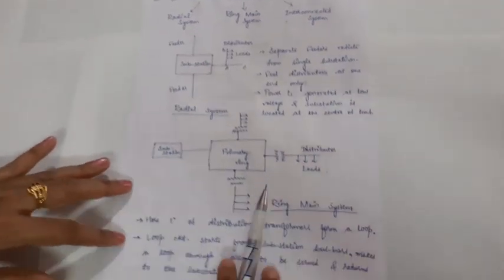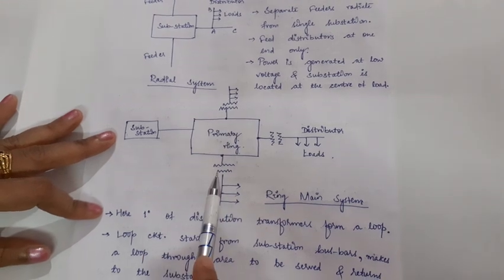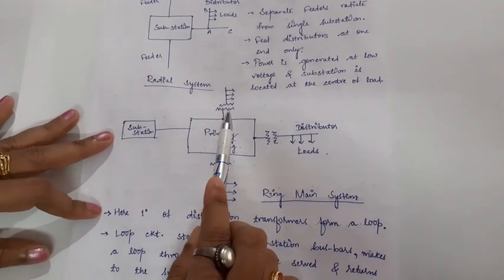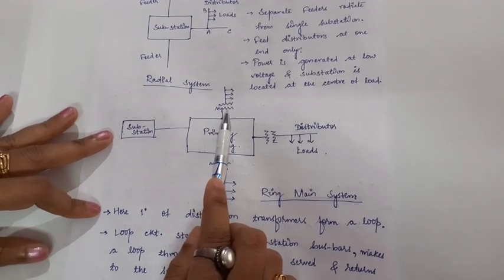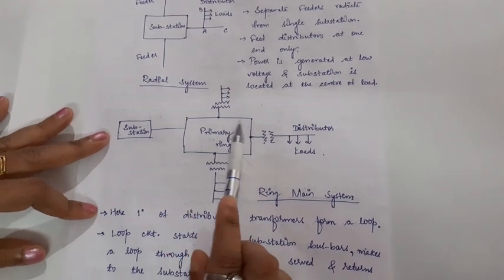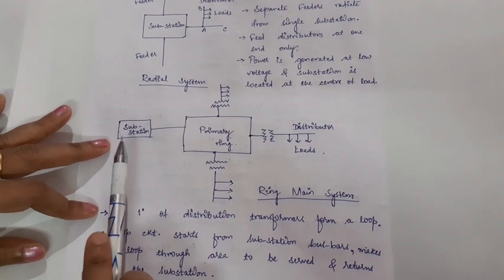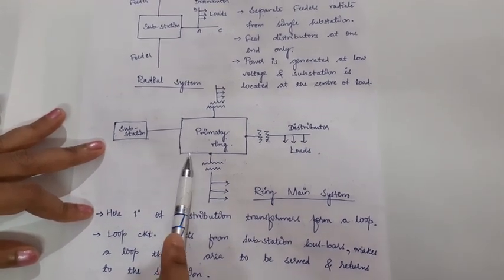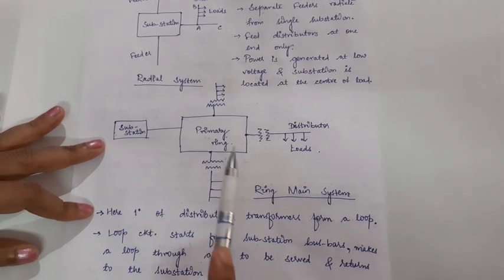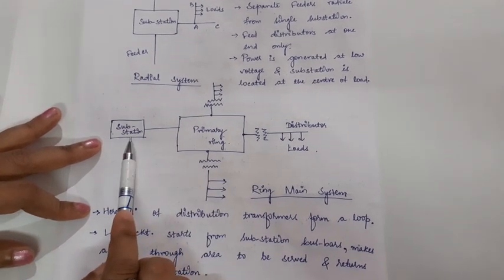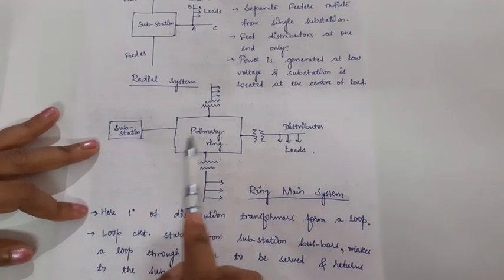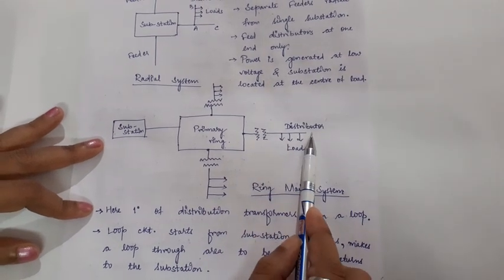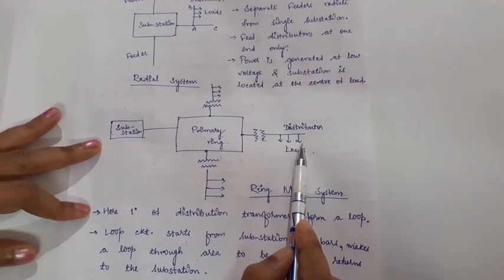In the ring main system, the primary of the distribution transformers forms a loop called the primary ring. The loop circuit starts from the substation, takes into account the substation busbars, makes a loop through the area to be served, and returns back to the substation. From the primary ring, the primaries of distribution transformers are connected. These are step-down transformers. From the distribution transformer, the distributor is connected, and from the distributor, tappings are taken as service mains connected to consumer loads.